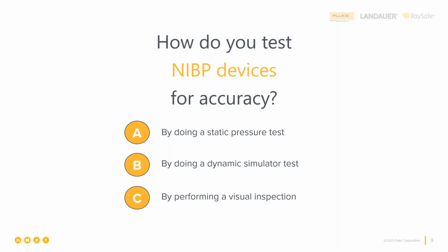Dynamic simulation is about repeatability and stability of the patient monitor measurement system, the whole system. It is not about accuracy. The dynamic simulation is not about accuracy. It's about other things. So our correct answer here is A, by doing static pressure tests. And those of you that have been doing dynamic simulation tests and thinking that you were testing accuracy, I'm sorry to inform you that that is not a correct way to think about it. You've been doing a type of testing that's necessary, but it's not about accuracy at all.